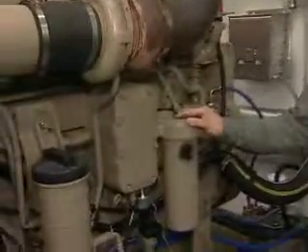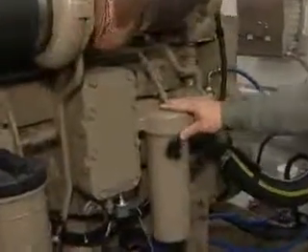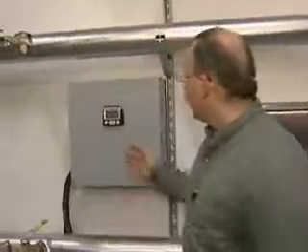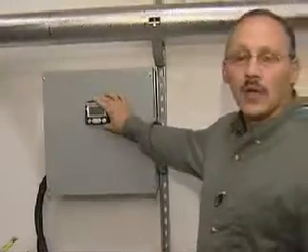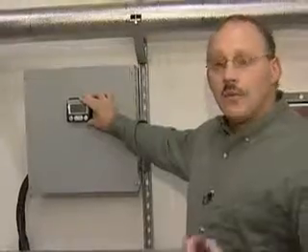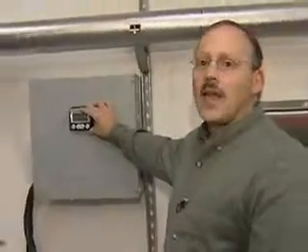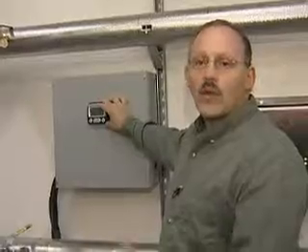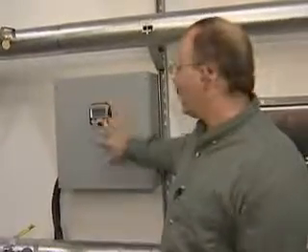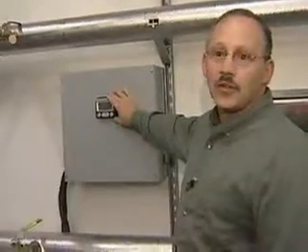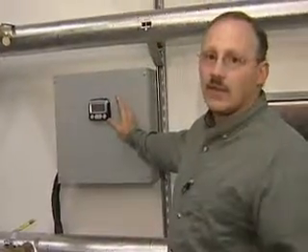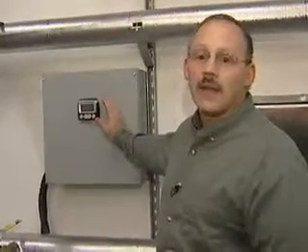More and more engine manufacturers are coming out with electronic fuel-injected engines. The difference is they do not have a fuel injection pump, and you don't have the external fuel lines like you would on a typical mechanical engine. With these, they also have newer electronic instruments that monitor all the functions of the generator — oil pressures, water temperatures, and hours of service are all indicated on these display screens. That's how the electronics give you all the information you want on the engine.